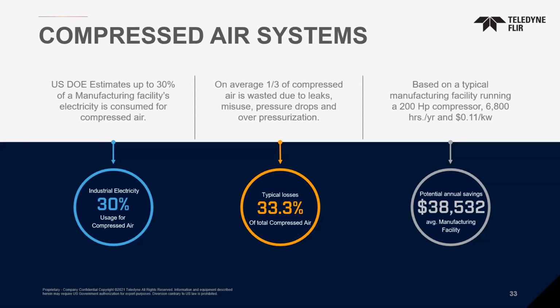If you extrapolate this on a typical manufacturing facility running a 200 horsepower compressor, say 6,800 hours a year at 11 cents a kilowatt, that means they're leaking $38,000 worth of air. That's doing no good - it provides no value to the company. It's a negative $38,000 on your profit, on your bottom line.